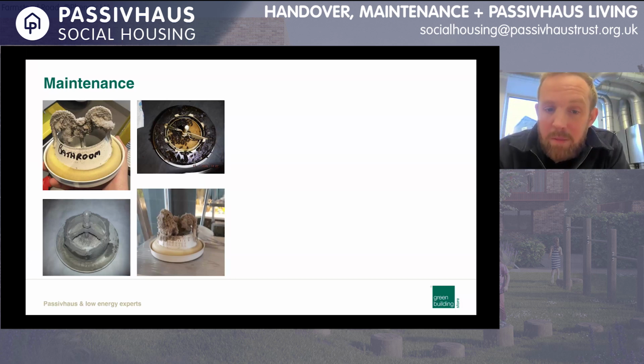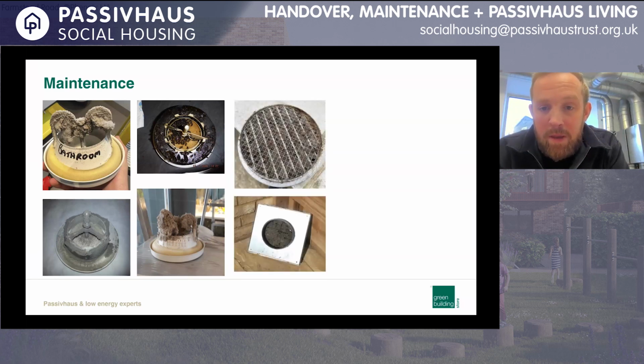Obviously, the bottom right one, there is quite a considerable buildup of dust there. That one, I think, was 5 years. And then on the top right, that's a kitchen extract where they didn't put a filter in it. So any designer really should be looking to put a filter in there, because it's attracted insects that have got trapped in there. And then we've got the intake grills. So you can see that's got an insect mesh on it, and it's collected airborne debris, there's animal hairs, there's bits of leaves, and the air is going to be really struggling to flow through there.